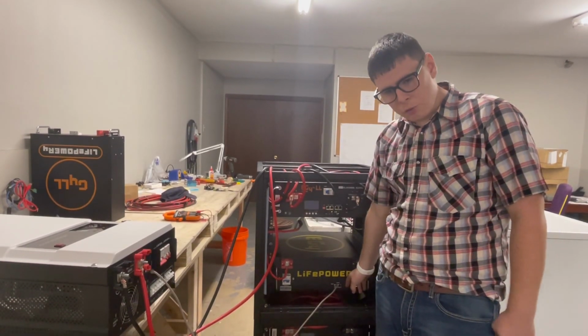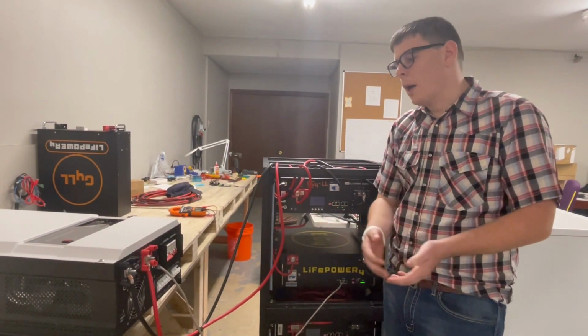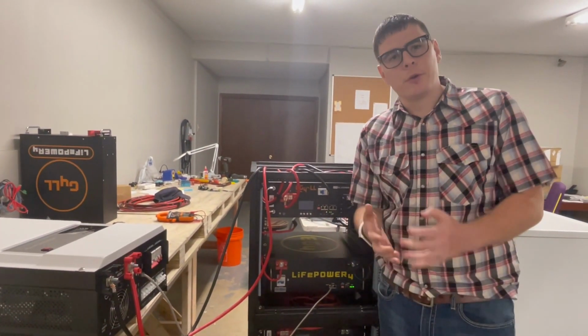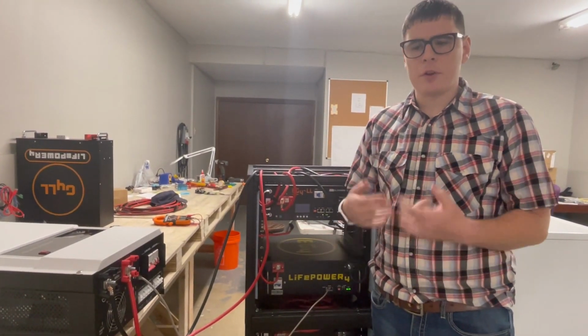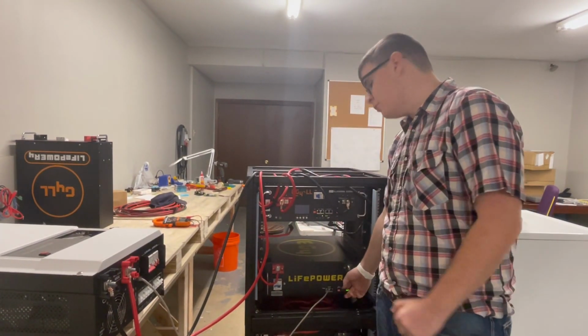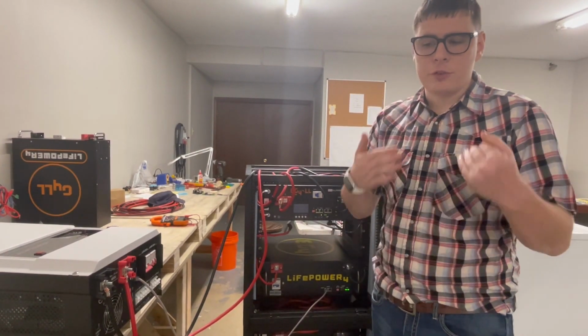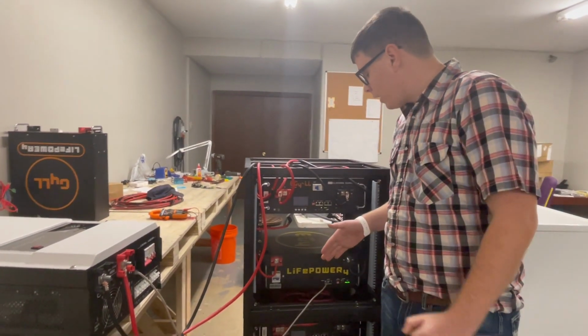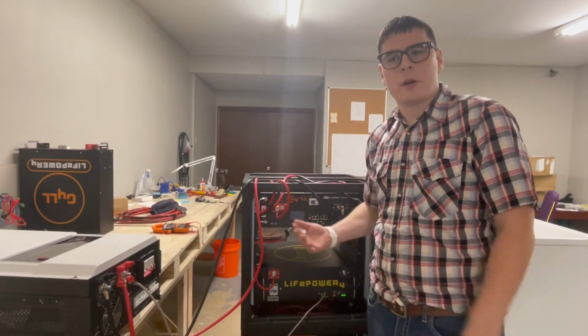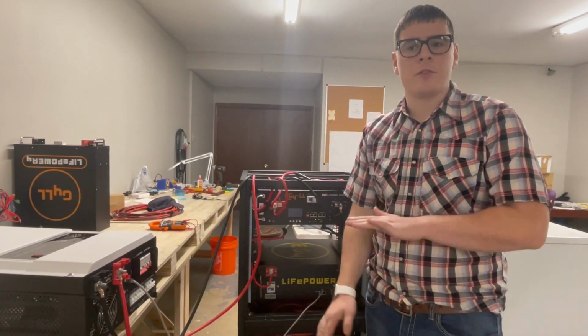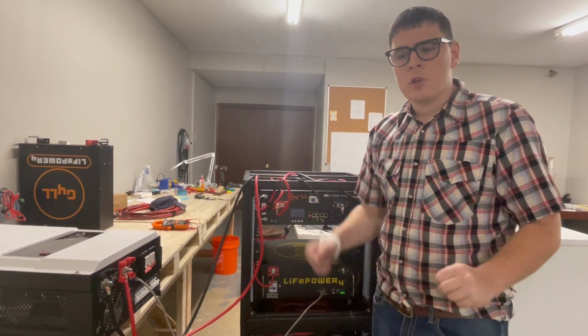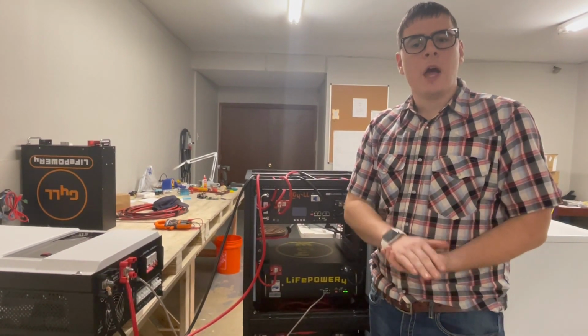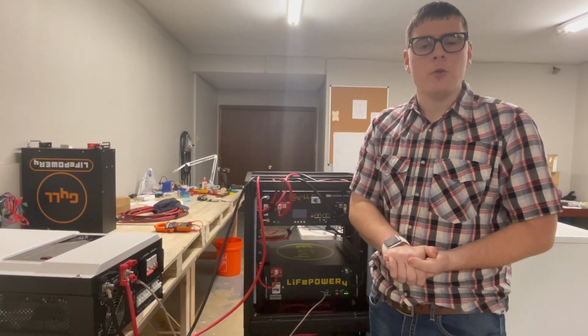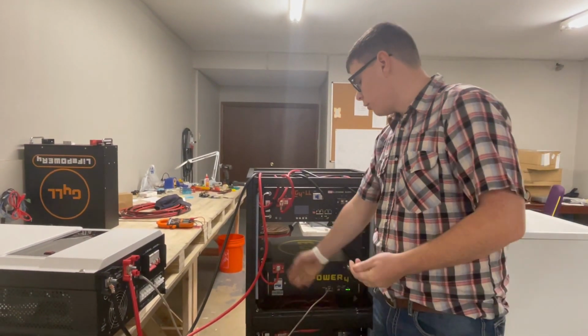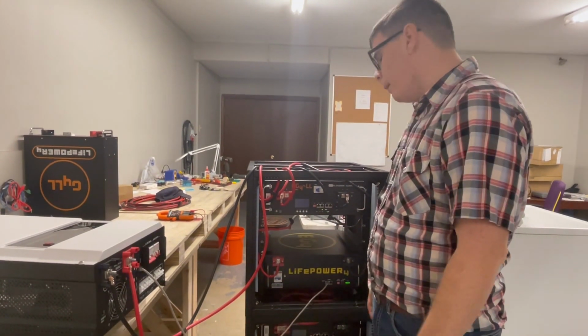if you set the address to address zero, you may have to reboot your battery in order for that address to take. Whenever you change addresses, you can't just flip switches and the address is different. You've got to actually turn the battery on and off. So if I had a second battery and it was at zero and I didn't want to create a conflict, I'll change all my addresses and then reboot all my batteries. So always reboot your battery after you've got the address set the way you want it, just for a precaution. It's just turning the power switch on and off and letting it boot cycle.